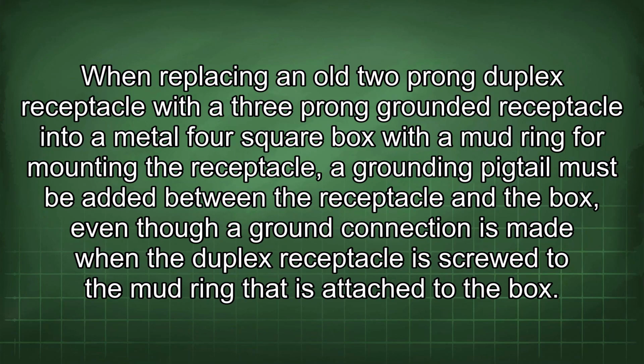When replacing an old 2-prong duplex receptacle with a 3-prong grounded receptacle into a metal 4-square box with a mud ring for mounting the receptacle, a grounding pigtail must be added between the receptacle and the box, even though a ground connection is made when the duplex receptacle is screwed to the mud ring that is attached to the box.